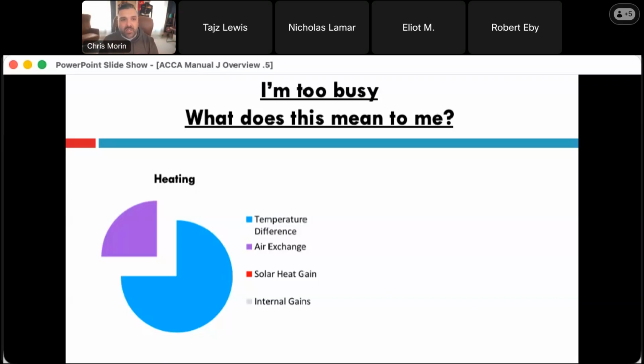Unfortunately, what this doesn't include when you use some of the simple calculators is infiltration or the air exchange. And what ends up happening is if you use some of these simple calcs or rules of thumb, you could be off easily by 25% when it comes to heat loss. That doesn't sound like a lot, obviously, for Austin, because we're focusing on the cooling side down there with air conditioners and heat pumps. But when you do need it, if you didn't take into account the 25% that you needed, it's going to have a problem keeping up, right? And it's obviously more magnified in the cold climates around the country.